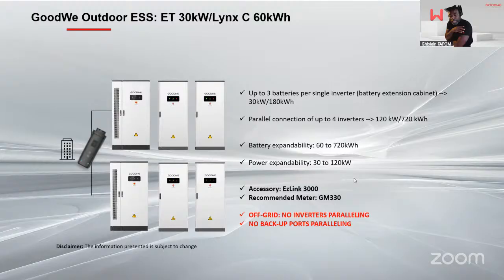And just a little note here: this system will not be able to be paralleled if it's off grid. So if it's off grid, you're only going to have one cabinet for the inverter and a maximum of 3 cabinets for the batteries. So the maximum will be 30 kilowatt to 180 kilowatt hours if you want to be off grid. And also the backup load cannot be put in parallel on this system. So these are the 2 notes of caution for this ET30 BESS solution.